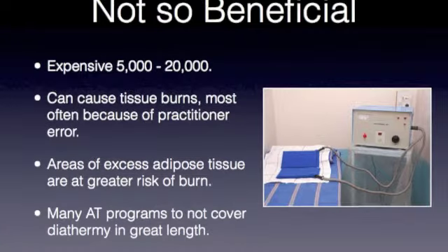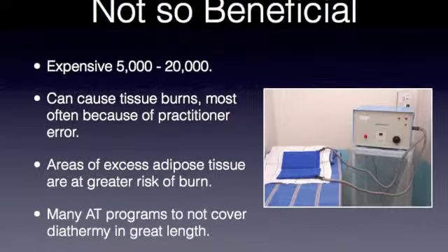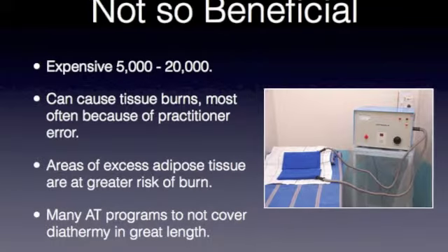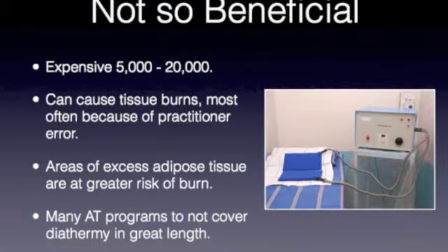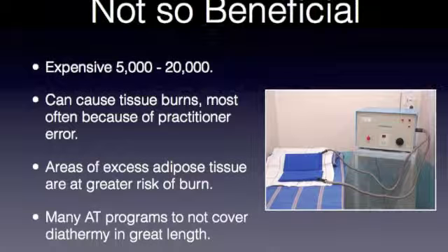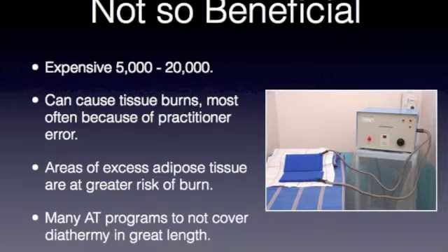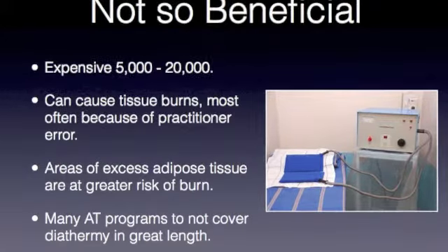Some factors about diathermy that are not so beneficial are that the units are pretty expensive, anywhere from $5,000 to $20,000 for a unit. As I stated before, this treatment can cause tissue burns, but most often it's because of practitioner error. There are specific requirements for setting up and using electrical currents, and it is not as dummy proof as some of the other machines that we use. So basically, you really have to know what you're doing.